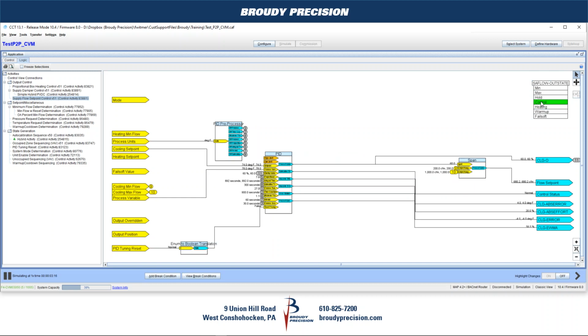If we go back again, green is signifying that's the current mode that we're in, and this is the wire sheet being used. Because basically what the state table is doing for us, a big part of it is, I'm used to with other systems, on the PID, you're going to have fan status or some kind of an enable to disable the integral and derivative portion.